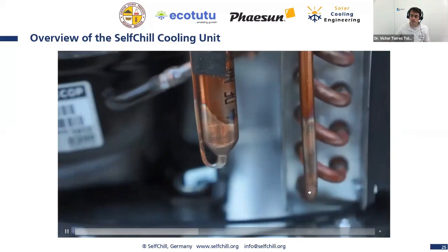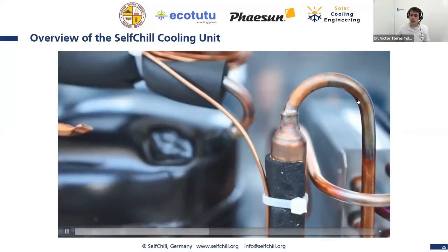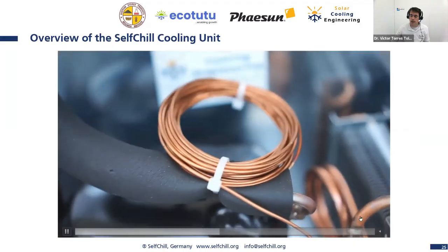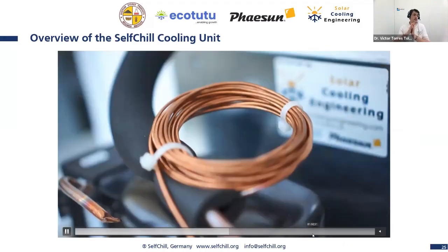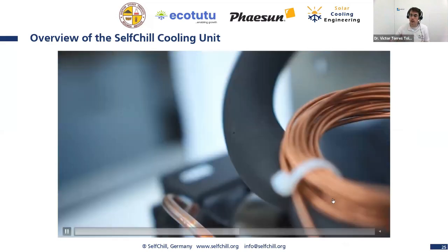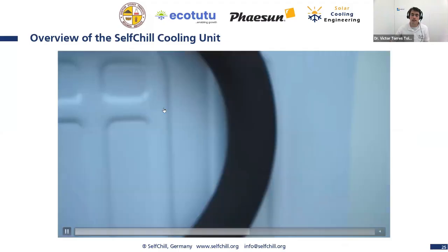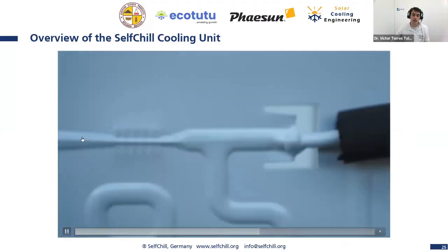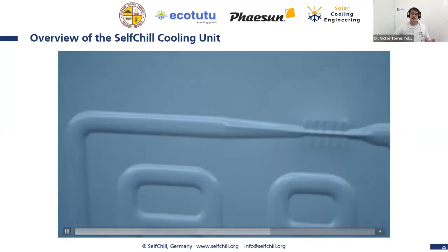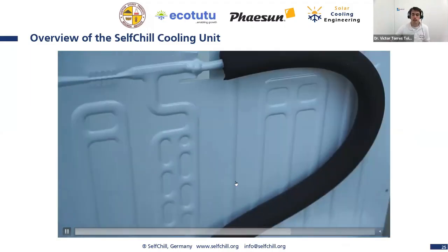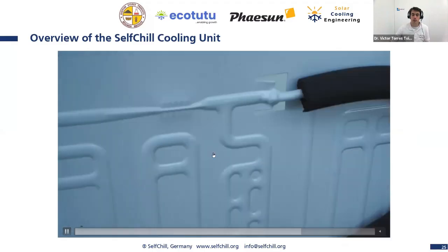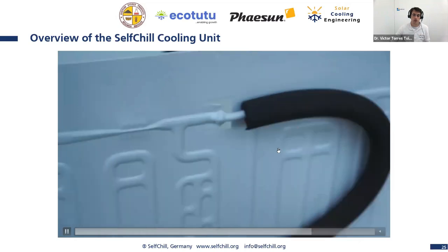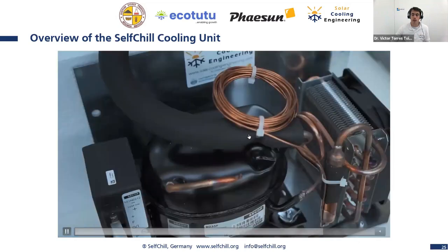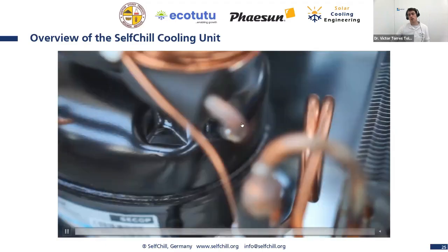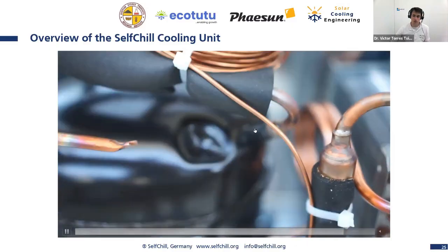Let's have a look here. This is the outlet of the condenser. Then it is going here to our capillary tube, which is in this case the expansion valve. So we are expanding the liquid over the capillary tube, which is inside this pipe and ending in the evaporator plate. Let's have a look here. You can see it. Can you see it? There the liquid is expanding. So it has a lot of space and then it starts to evaporate, producing cooling energy, going up and down in the evaporator plate. And then at some time coming back as vapor again, going back to the compressor. So here we have been able to recognize all parts of a heat pump. So this is a closed cycle, so to say.